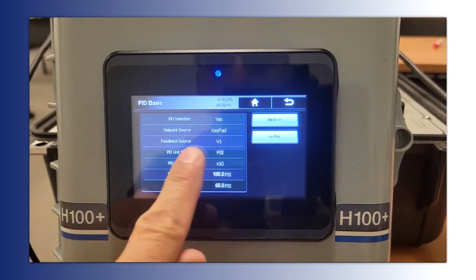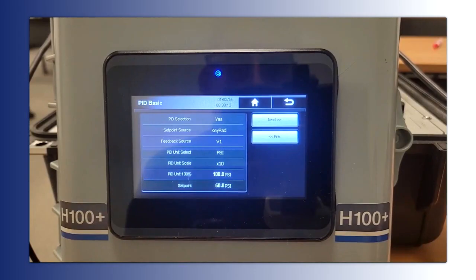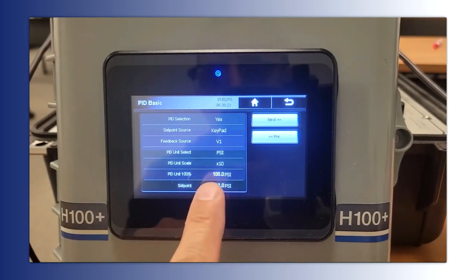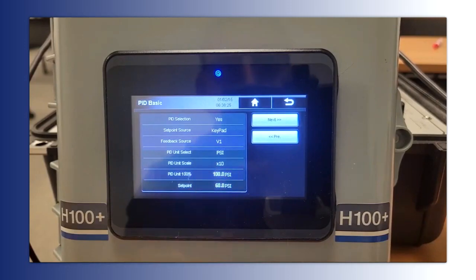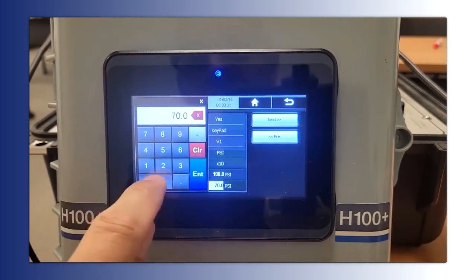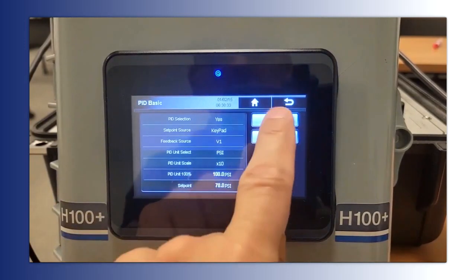In the real world, you'll probably be doing a 4 to 20 milliamp feedback on I2. In this case, we have a speed pot. We're simulating feedback. So I have it set up for V1, 0 to 10 volts. PSI is our units, 100 PSI is the max scaling of our transducer, and we have a set point of 60. So again, this is point and click. So I'm going to change it to 70 PSI and hit next.